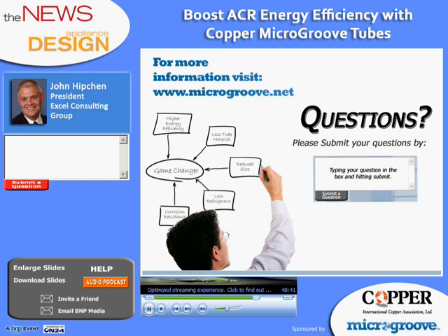Is MicroGroove the same as inner grooved tubing design? It is, as far as referring to the internal patterns that enhance heat transfer in a round copper tube. MicroGroove, though, the way it's being used by the International Copper Association, refers more to the smaller diameter internally enhanced copper tubes.